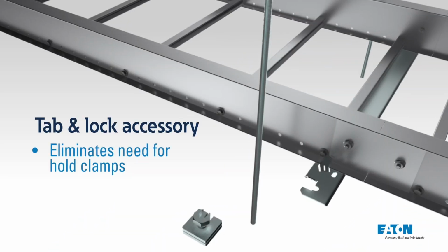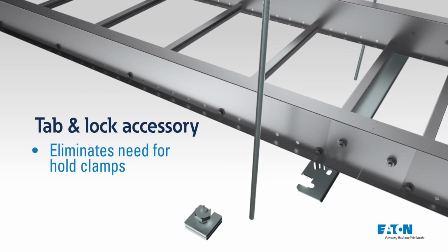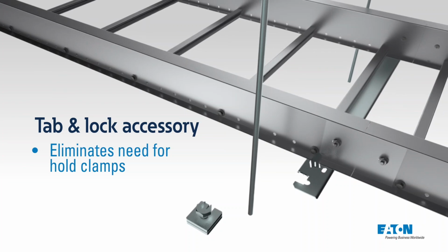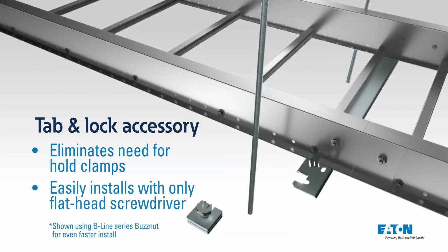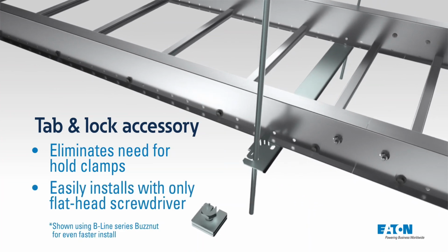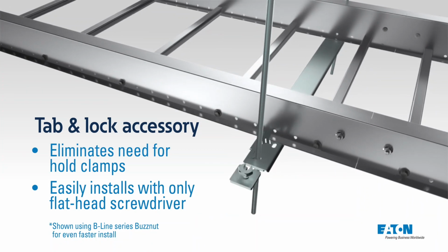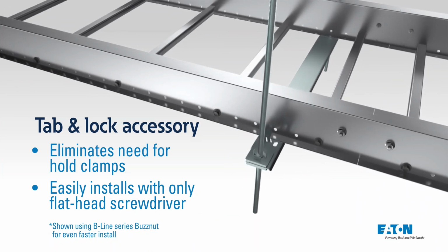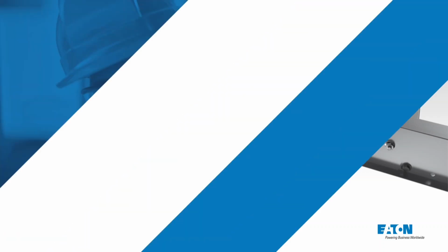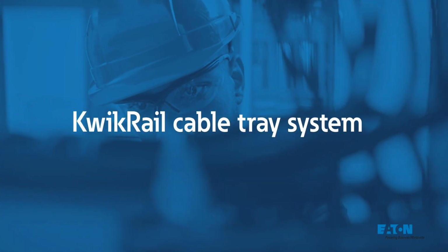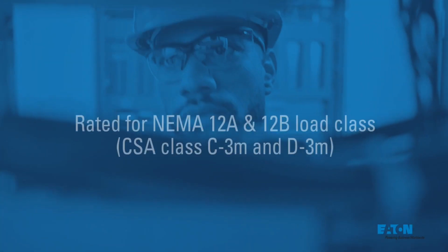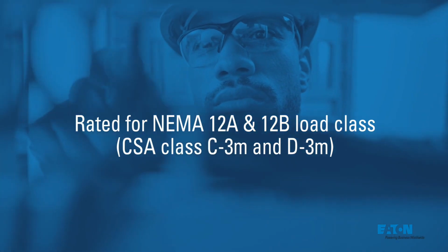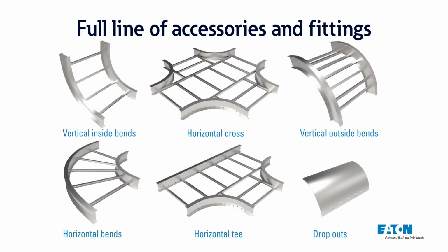For a quicker trapeze assembly, we offer the tab and lock solutions, which eliminate the need for hold-down clamps. By simply using a flathead screwdriver, the installer can position and lock the trapeze onto the threaded rod and then clamp the cable tray to the support assembly. The Quick Rail cable tray system is ideal for any project requiring a 12A or 12B load class. The system includes a wide range of straight sections, fittings, accessories, and covers.